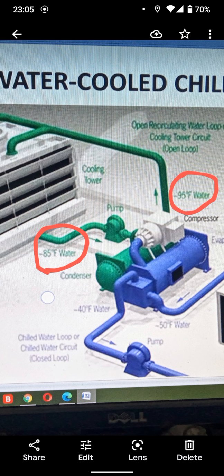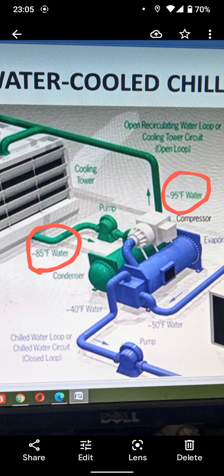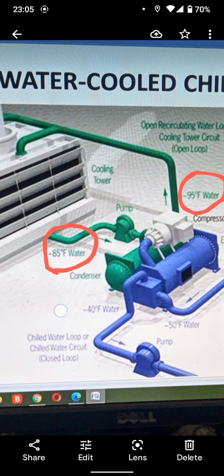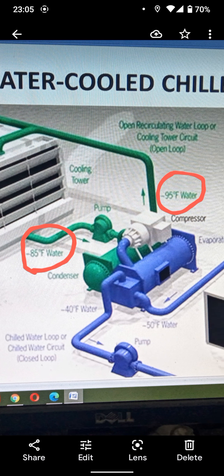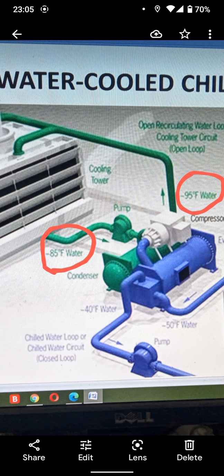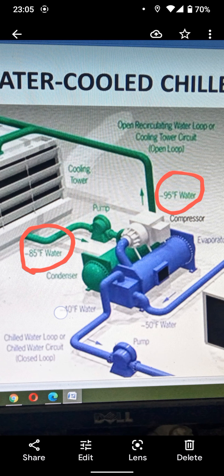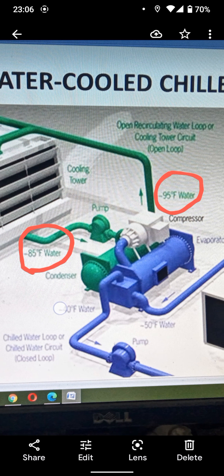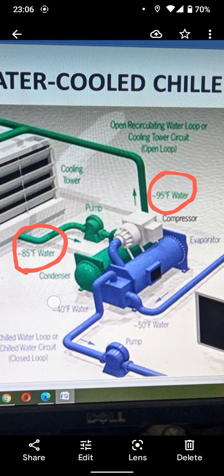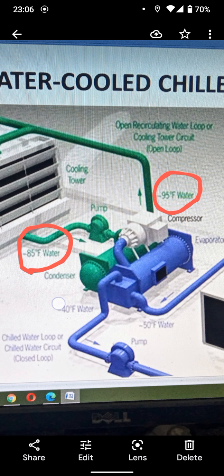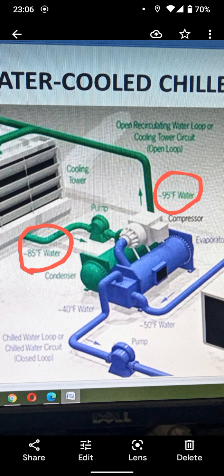I did this one. Maybe you are the technical guy. What will you do when you see the cooling tower giving, instead of 85, a supply of 94 on height? Will you change the cooling tower? What do you do? Do you put ice cubes in the cooling tower water tank to cool down the temperature? No. In this situation, you have to do something to run the plant. You cannot expect that a book tells you, as per design, as per selection sheet, as per chiller requirement, we need 85. No, you cannot say that.